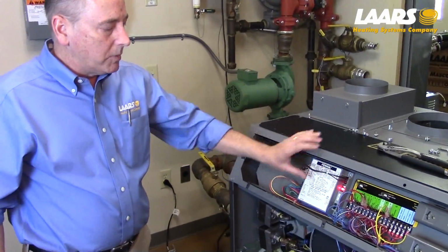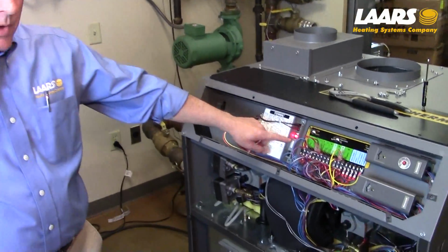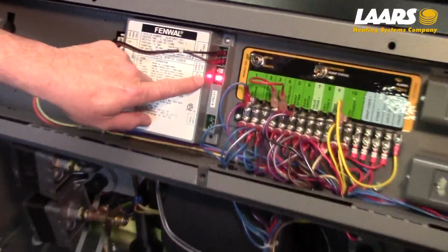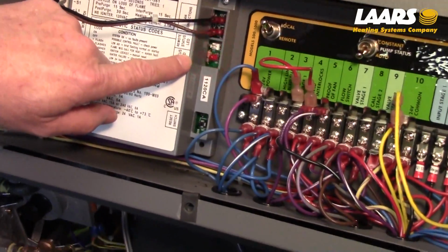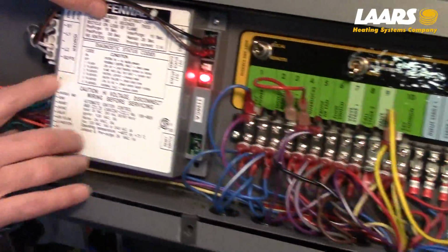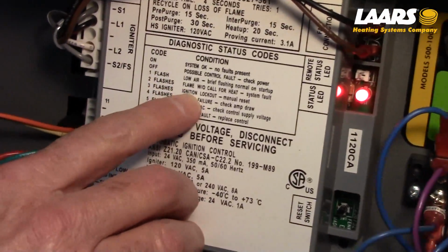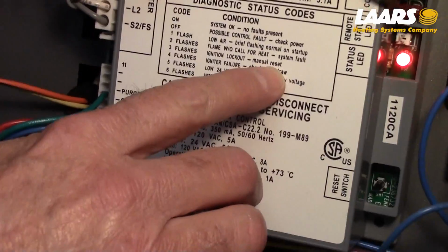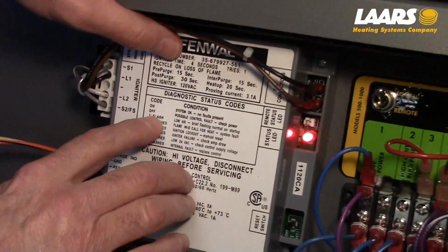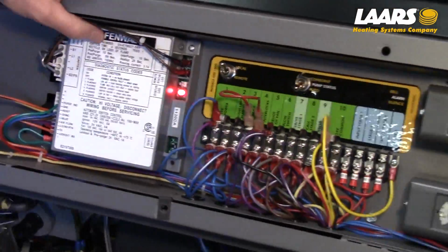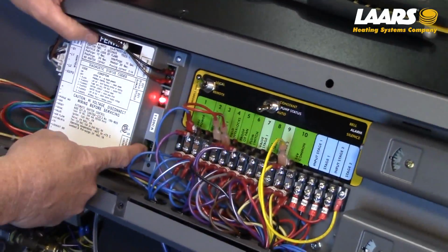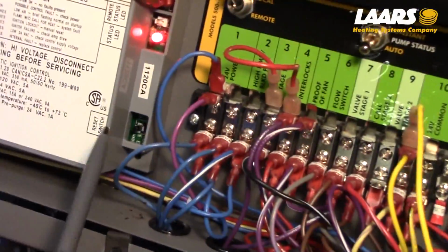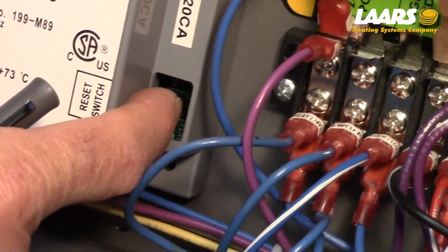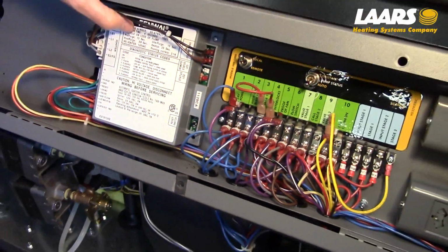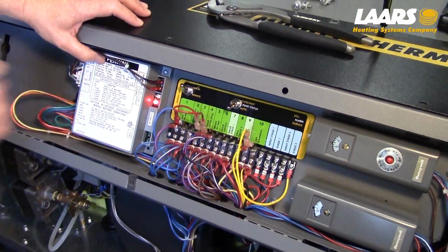Okay, lastly, I just want to talk about the ignition control and the fault codes. So, as we can see right here, we're flashing 3 flashes. And when you look on the codes here, 3 flashes will show you ignition lockout. It's a manual reset. So here are our codes. 2 flashes would be low air. So there's a reset button right here. That little black reset button right there. That is reset for the ignition control. So I'm going to press the reset button, and now we have a steady on line.